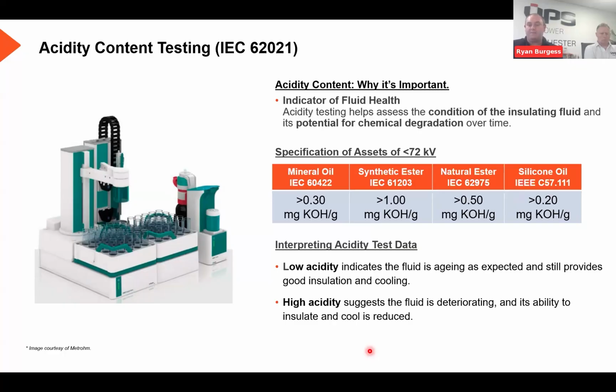But again, the basic principles when you're looking at that data are that a low acidity is good and shows that the cooling and the insulating properties have not been degraded yet, whereas a high acidity suggests degrading, and obviously the oil's properties have been reduced over time. The source is just general time and aging. That's the main source of why it appears. As it starts increasing over time, it just starts going up and up. So it's just one of them.